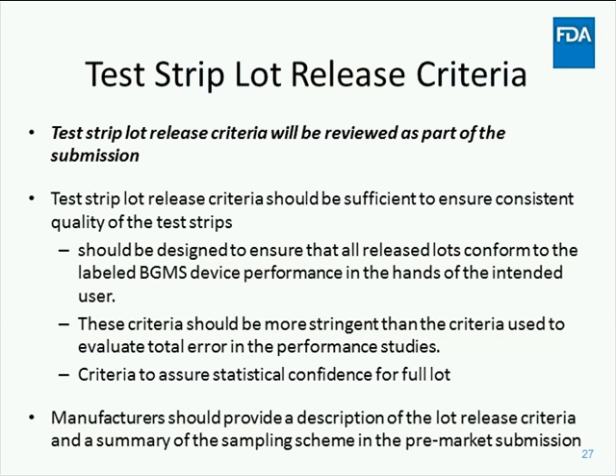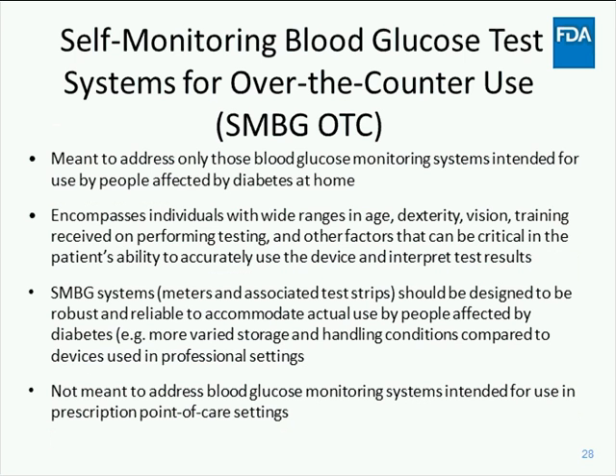They should be designed to ensure that release lots conform to the labeled device performance in the hands of the intended users. These criteria should be more stringent than the criteria used to evaluate total error in the performance studies. And these criteria should assure statistical confidence for a full lot. Manufacturers should provide a description of the lot release criteria and a summary of the sampling scheme and acceptance criteria in the pre-market submission.